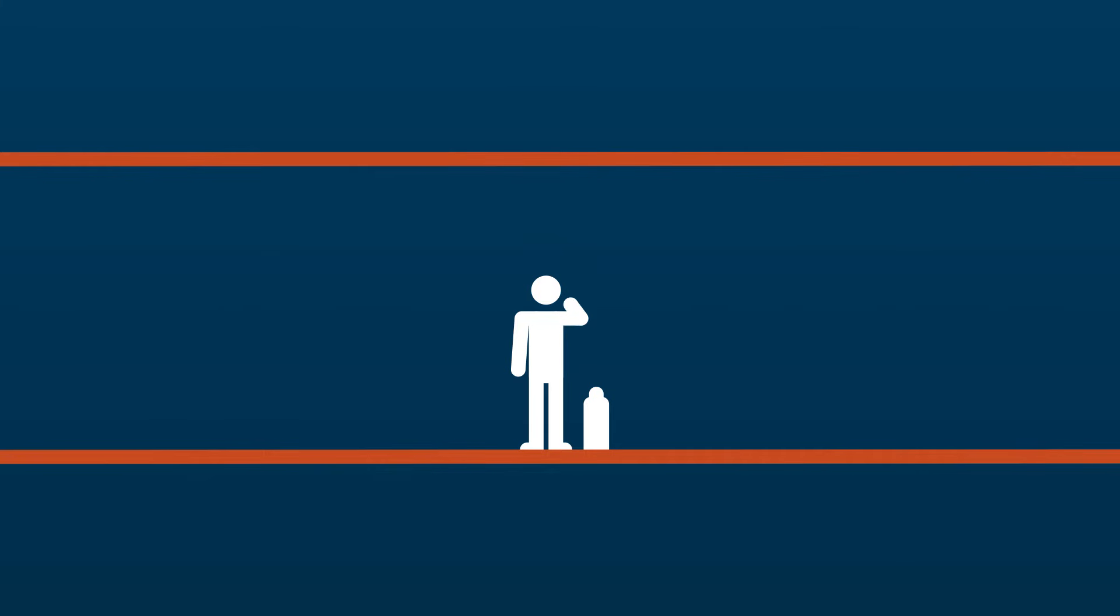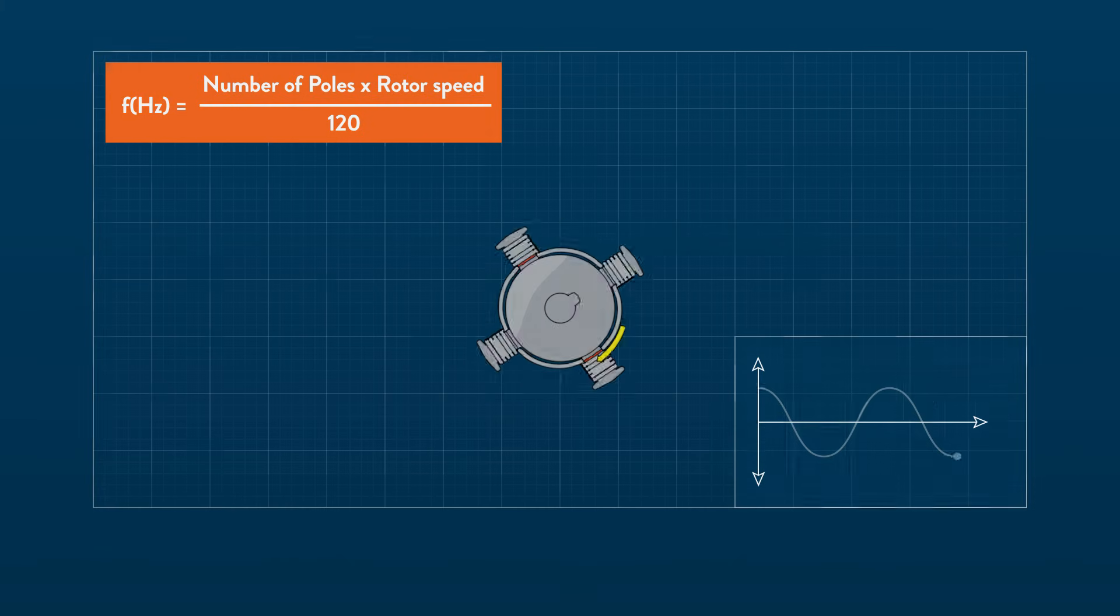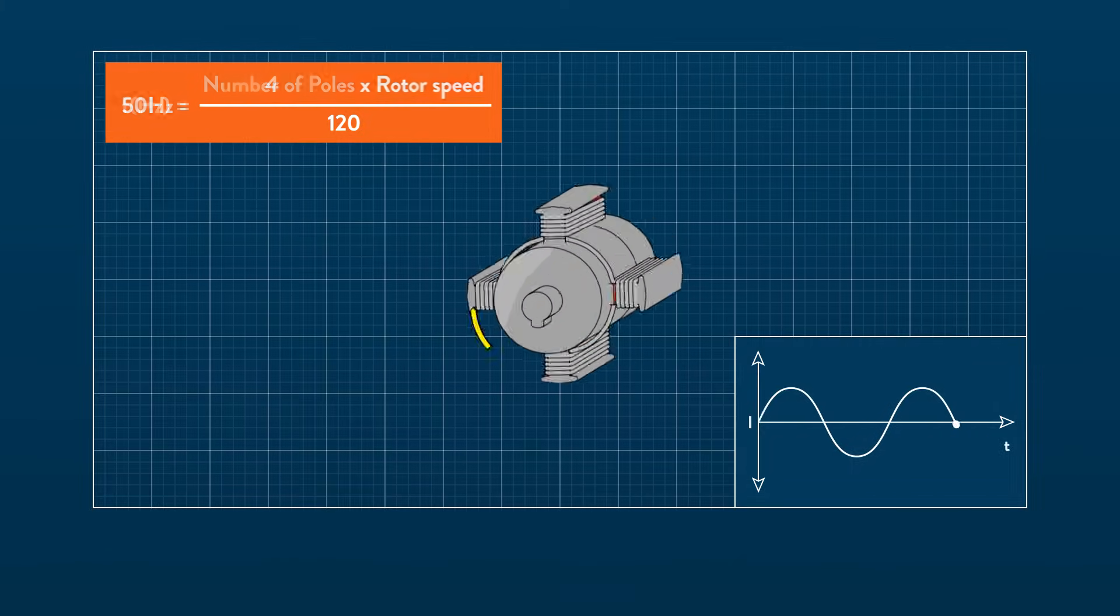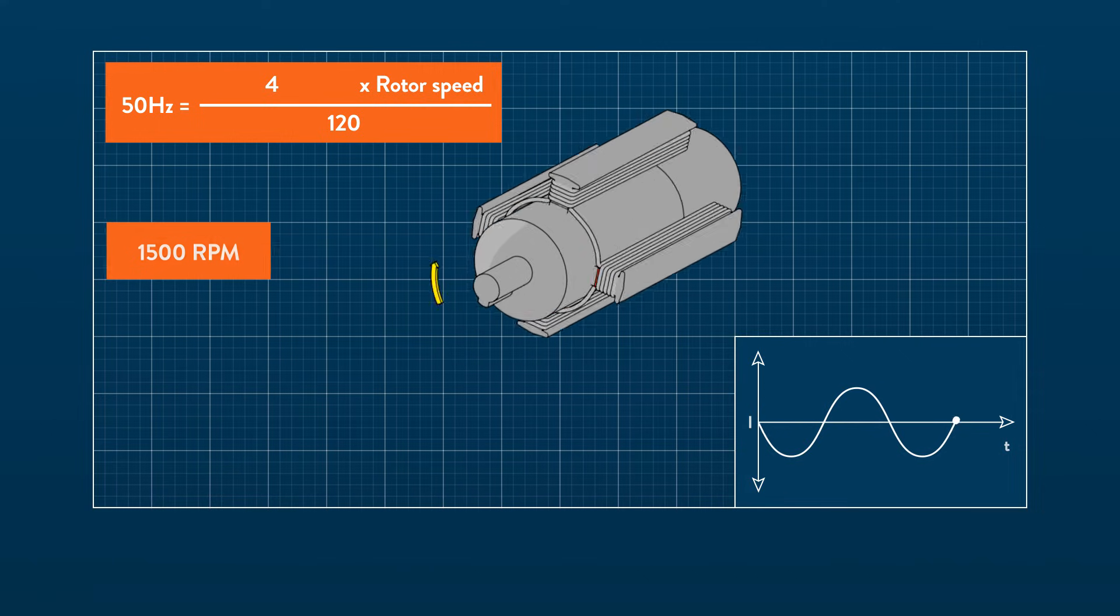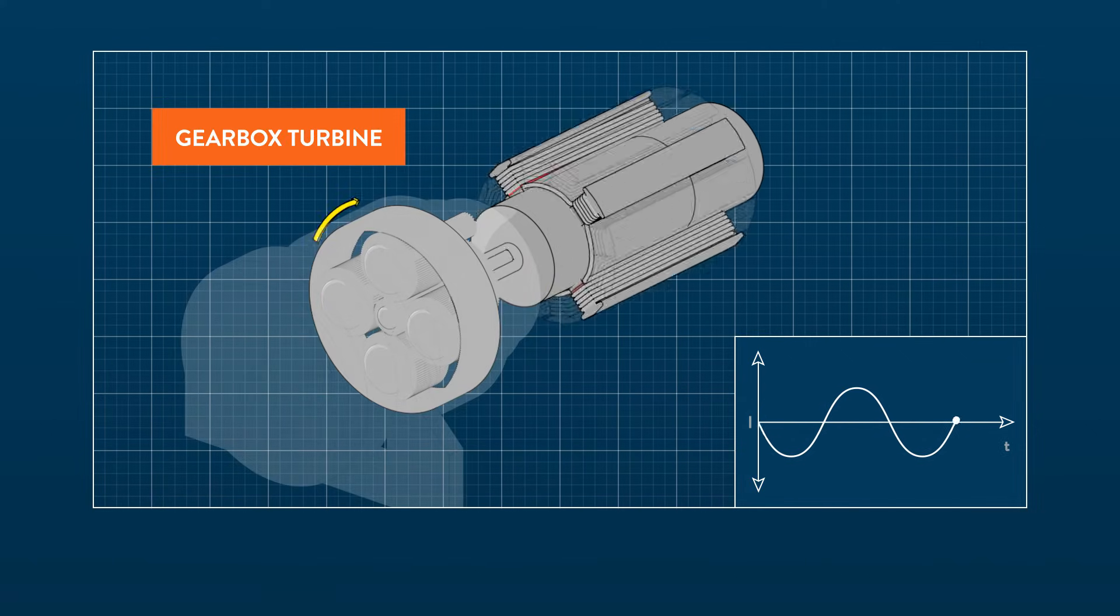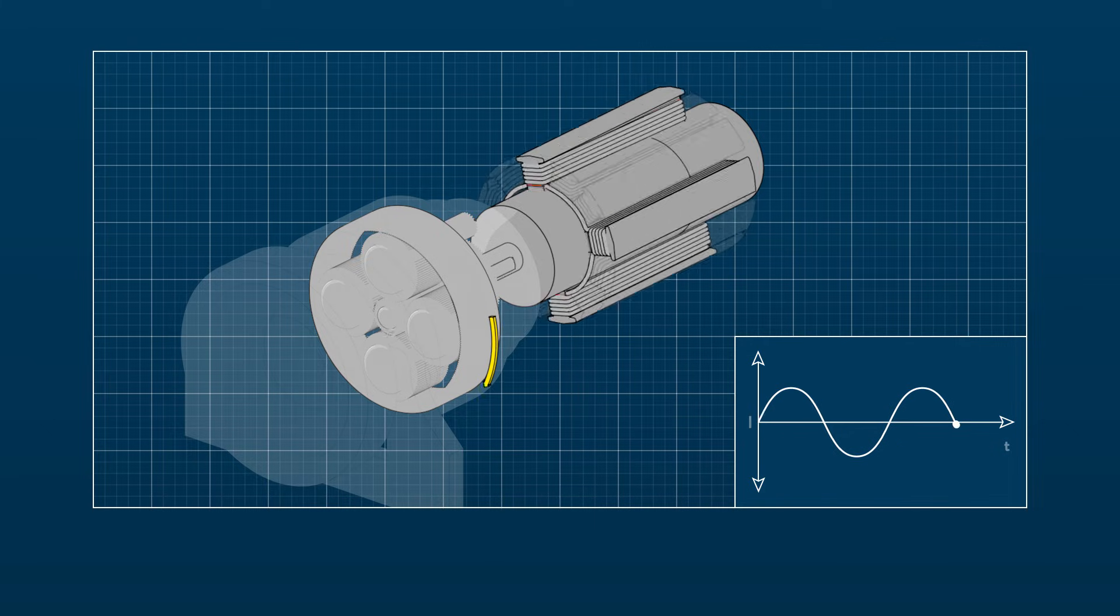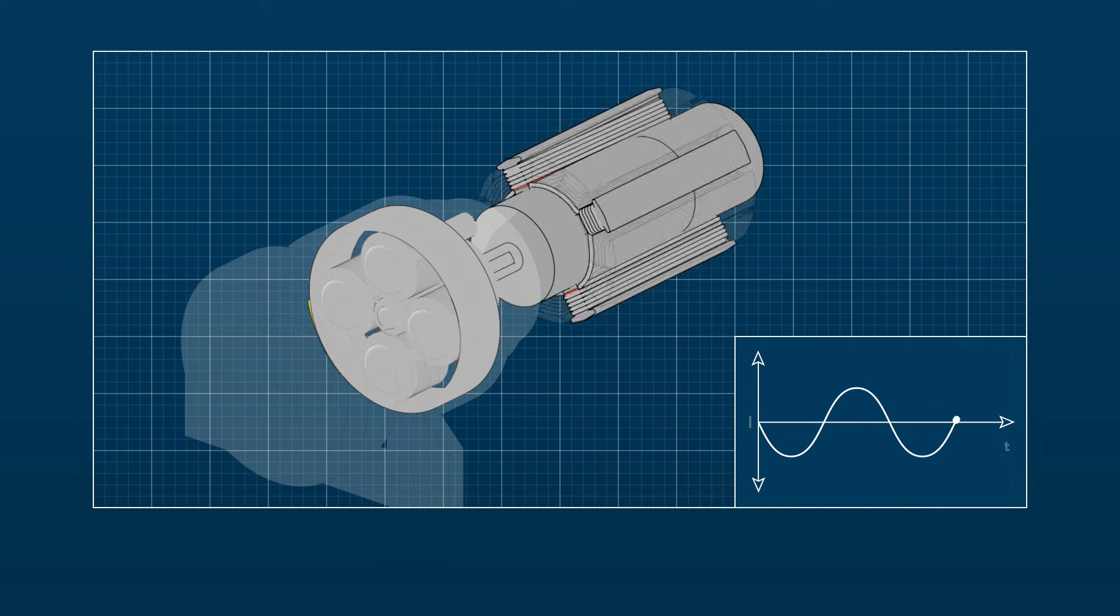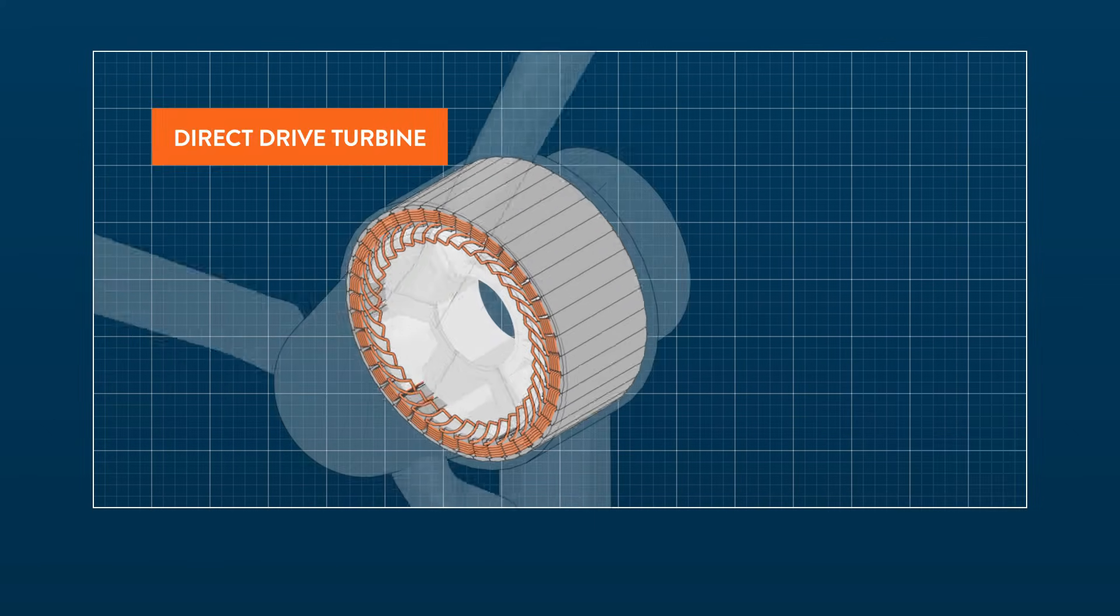And how do you board a moving train? In a four-pole rotor that is connected to the grid, the shaft will have to turn 1500 rpm. Gearbox turbines use gearboxes to increase the frequency of the rotor shaft. Direct drive turbines use more poles.